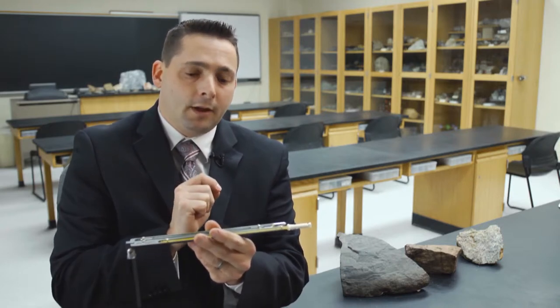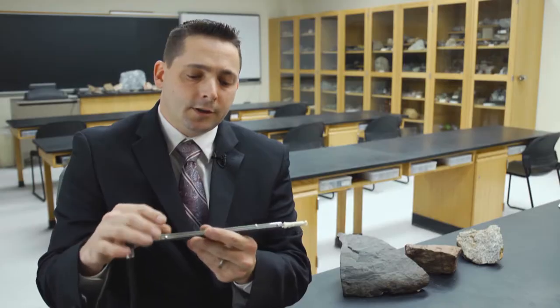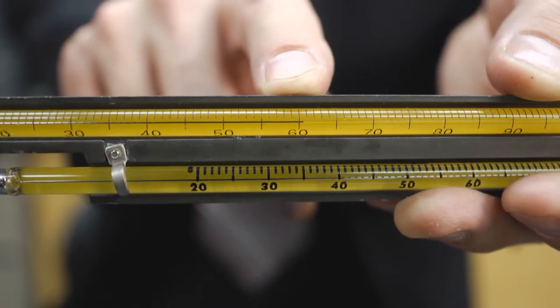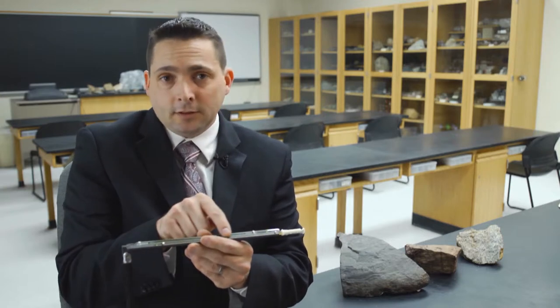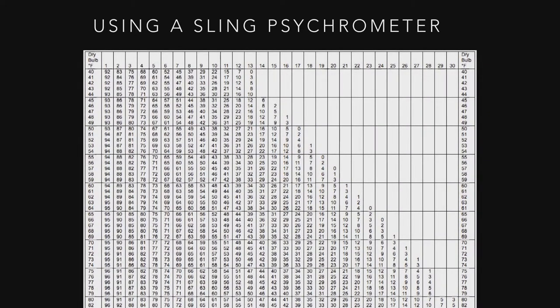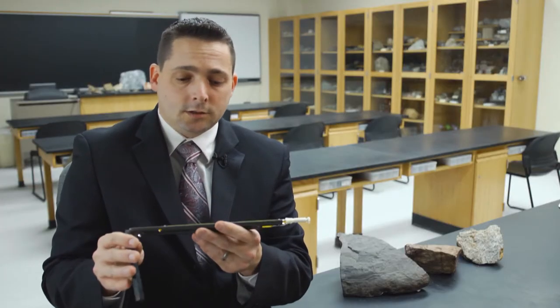Then all we need to do is measure the change in temperature on the wet bulb and locate that difference in temperature on a chart of relative humidity based on the temperature of the room. And we can easily determine the relative humidity on that day in that location.